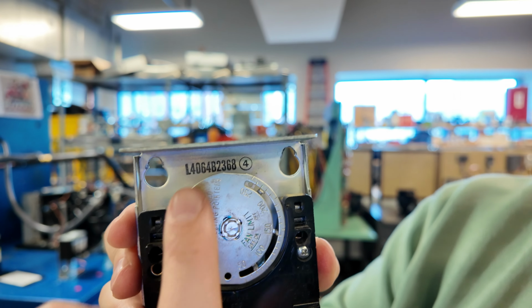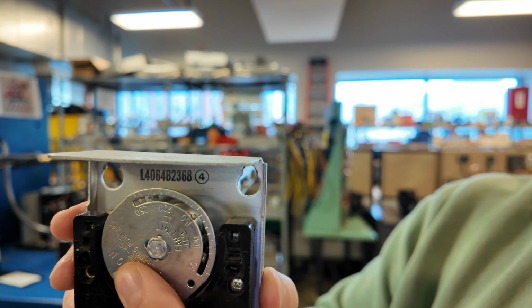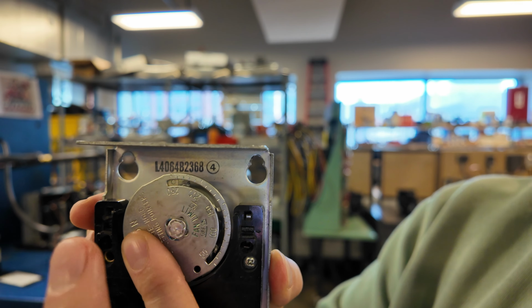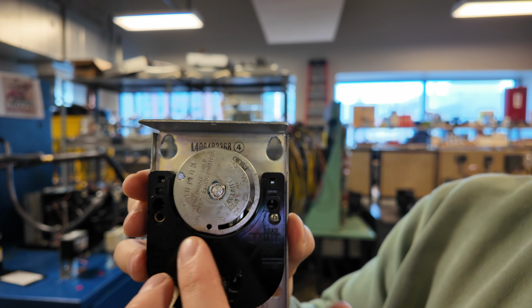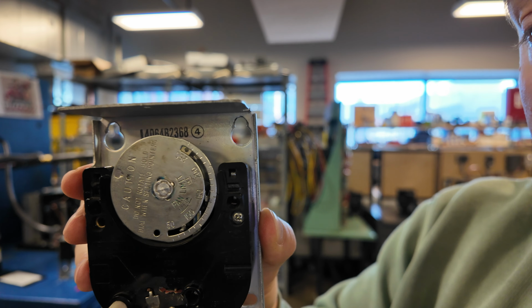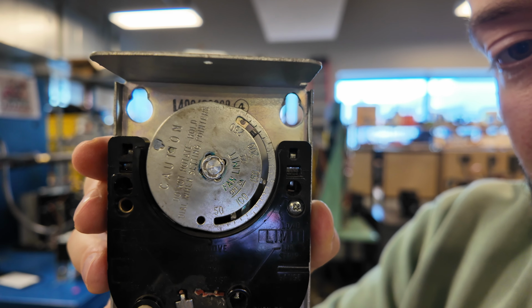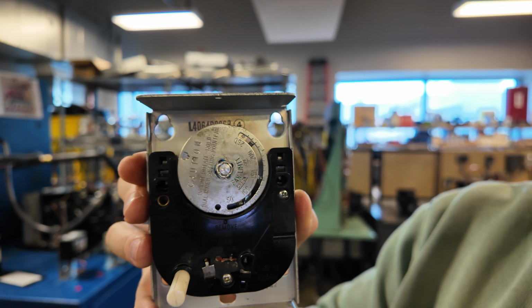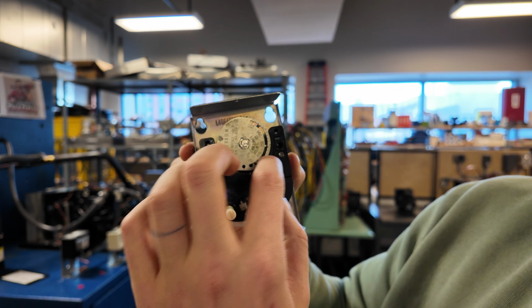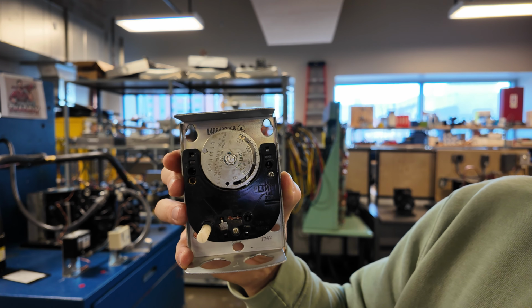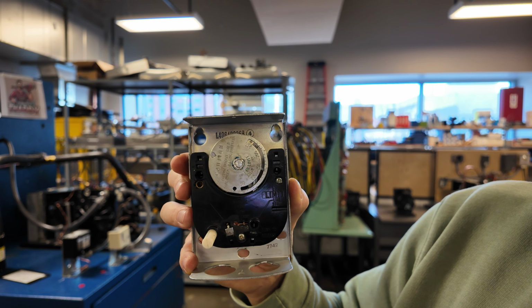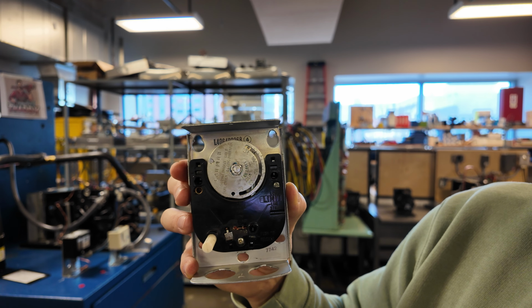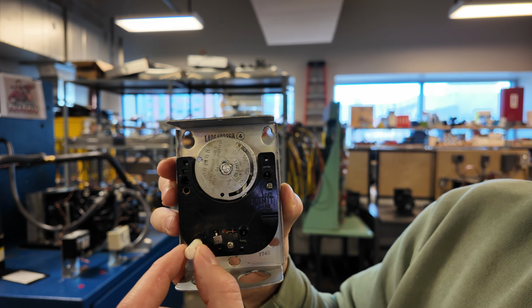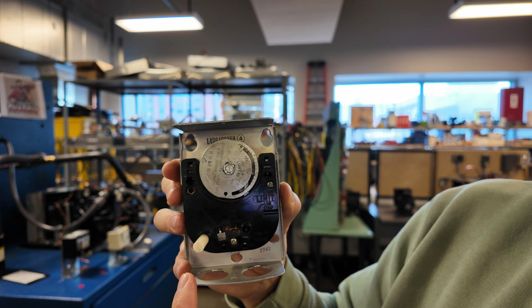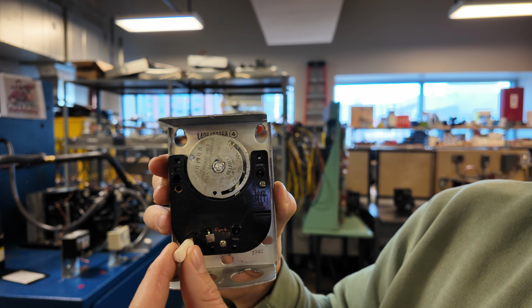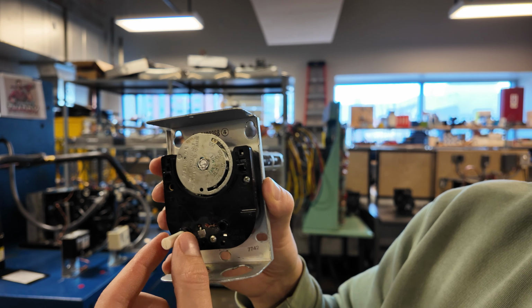So this bimetal strip, or spiral, when it heats up, it will twist. And what is it twisting exactly? See this metal piece here, see how I'm twisting it? When it heats up, it's actually going to twist. And there are these little hands here, and you're going to adjust these hands for cut out, cut in, and high limit. You'll have the ports here for connecting your wires going to the gas valve, through the high limit to your gas valve and to your blower. This tab here is to take your blower fan from auto to on.